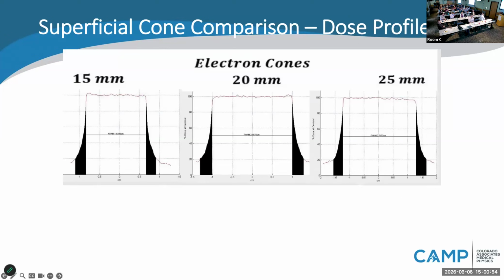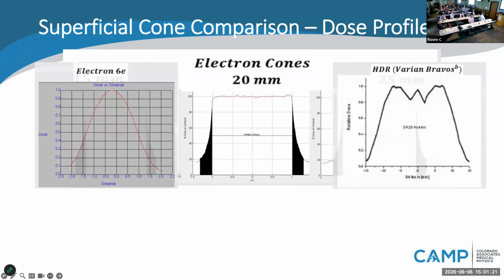And then in comparison, this is what our initial superficial cone profiles looked like. So 15 millimeters to the 25. Those numbers again might be a little bit hard to see, but that's not just a nominal value there. That's legitimately the treatment diameter that you're able to accomplish. And as you can see there, it's pretty much perfectly flat from edge to edge. In comparison, that's a profile from a 2 centimeter cutout from our old Pinnacle system. That's a 2 centimeter profile for a standard electron cutout. So even though it's a 2 cm circle, you only have 3 millimeters of prescription range. And then on the right there, that's from the Varian Bravos applicator. A little bit of a better job on the treatment width, but there are heterogeneities of 20% right here in the middle of the field.